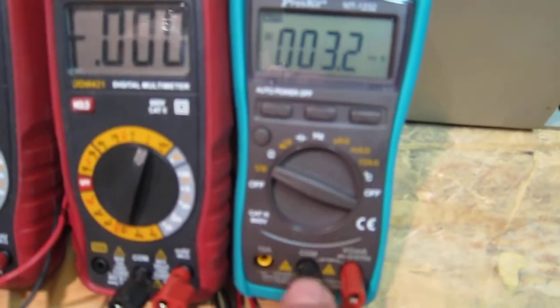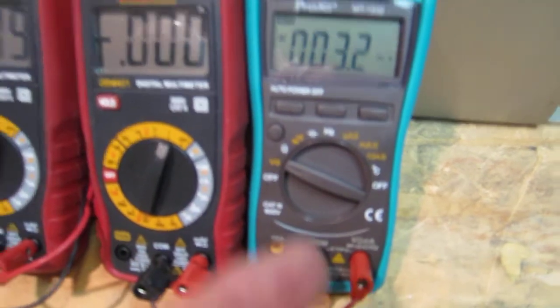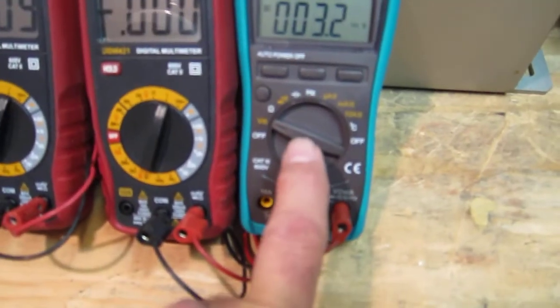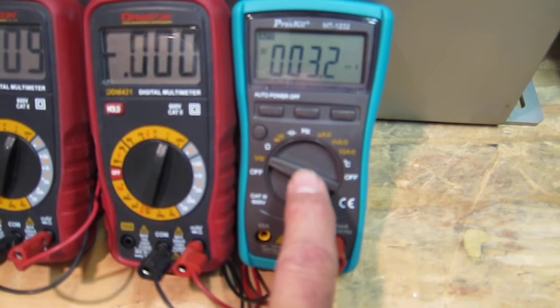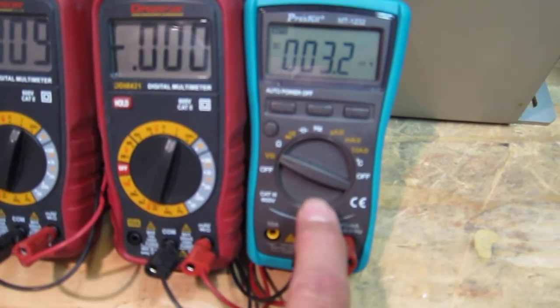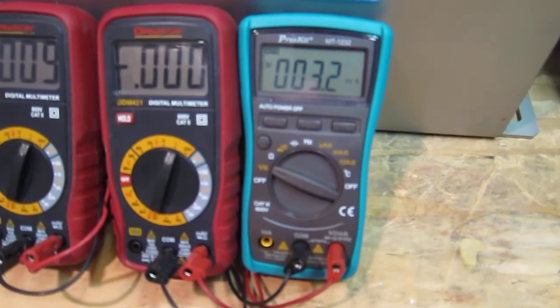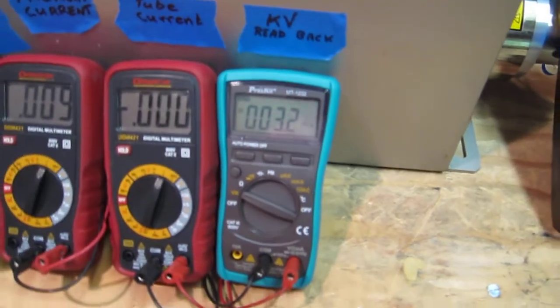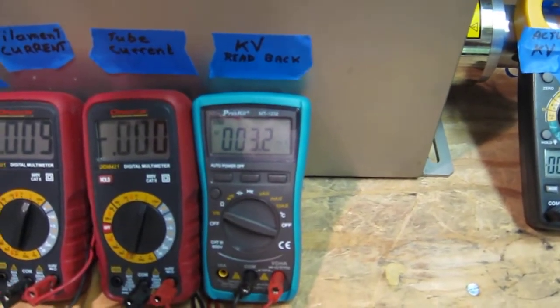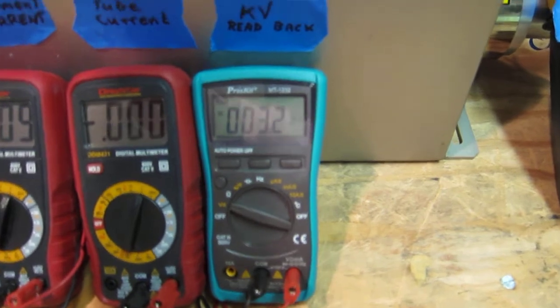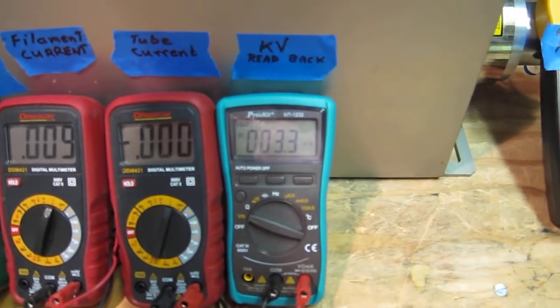And then over here, this is reading millivolts right now because it's just not all the way down to 0, and that's voltage coming out from the XRG-160 that normally would be reading kilovolts, and it's not going to be scaled to anything normal. I believe 1 volt on that is going to be 16 kilovolts.